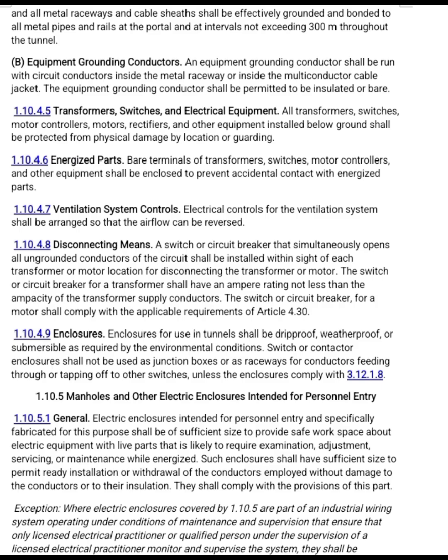1.10.4.5 All electrical equipment installed underground must be protected from physical damage by placing it in a safe location or adding guards. 1.10.4.6 Exposed live terminals of equipment must be covered or enclosed so workers cannot accidentally touch live parts. 1.10.4.7 Ventilation controls must be designed so that airflow can be reversed when needed. 1.10.4.8 Each transformer or motor must have a switch or circuit breaker located within sight of it. 1.10.4.9 Electrical enclosures in tunnels must be drip-proof, weatherproof, or submersible depending on conditions.